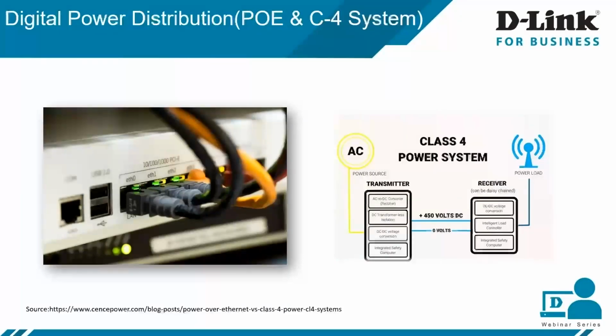Now a small introduction for class 4, which is also called fault managed power. If you are familiar with the National Electrical Code, you'll know there are 4 different categories for power systems or circuits, categorized under wiring methods in the code book as class 1, 2 or 3. This new power system rating, class 4, is first introduced after 45 years. Class 3 was introduced in 1978, and now in 2023, article 726, we first see class 4 introduced.